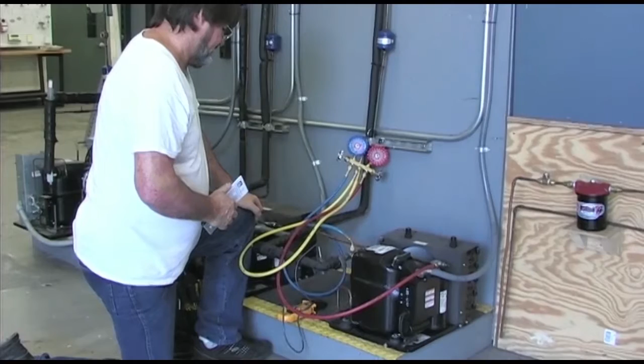What we're going to do next, Carlos is going to calculate the superheat for this low temperature refrigeration system that you would find in your local convenience store or at your supermarket. He's connected the red hose to the high side, the blue hose to the low side, which are connected to the gauge manifolds. He is currently reading the system operating pressures for this unit.